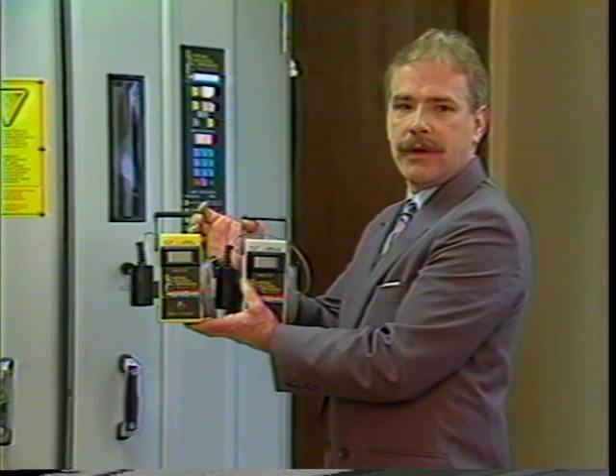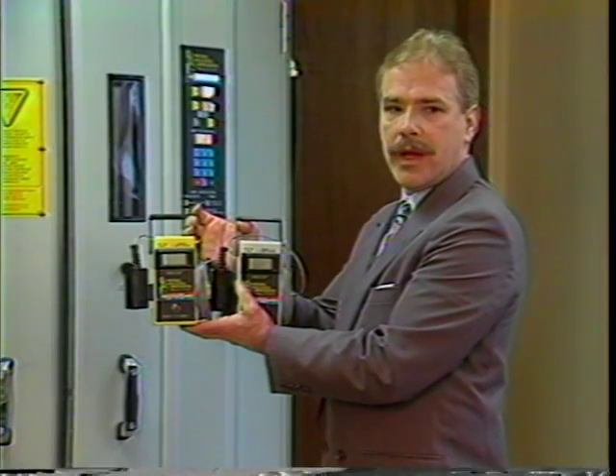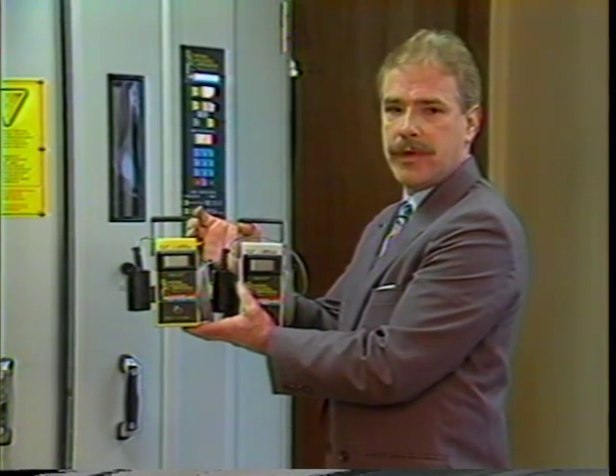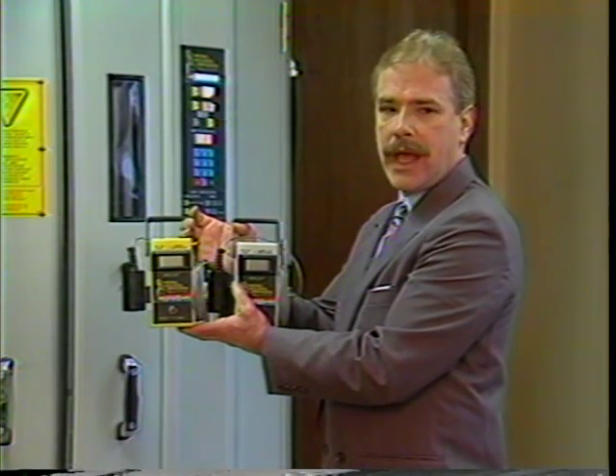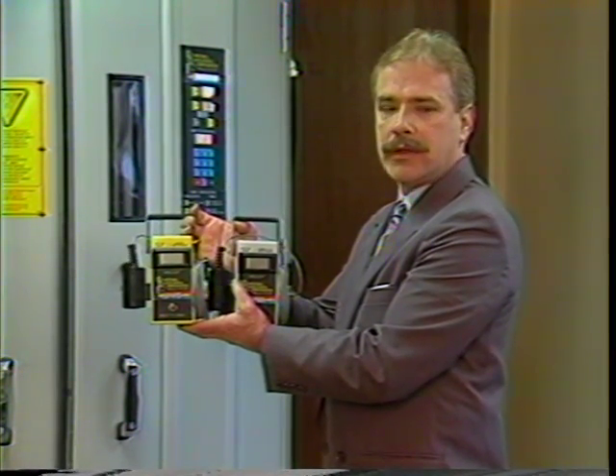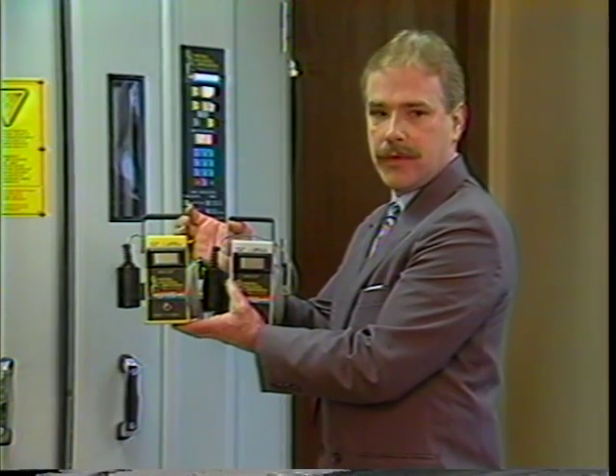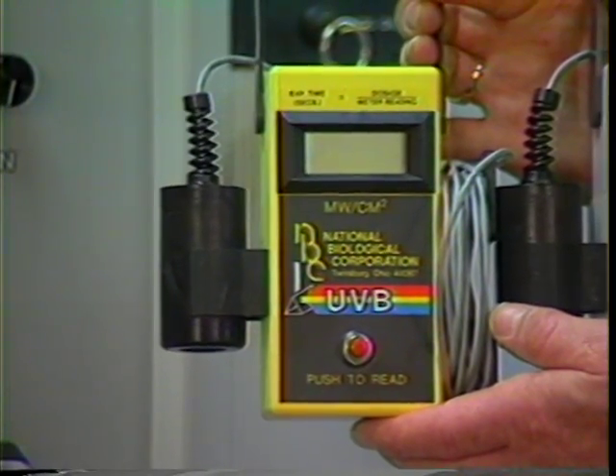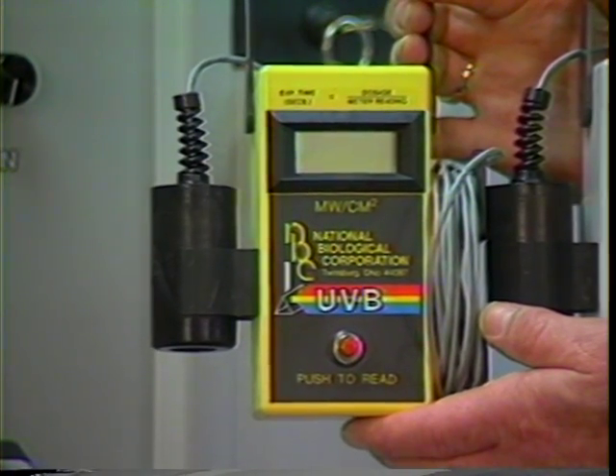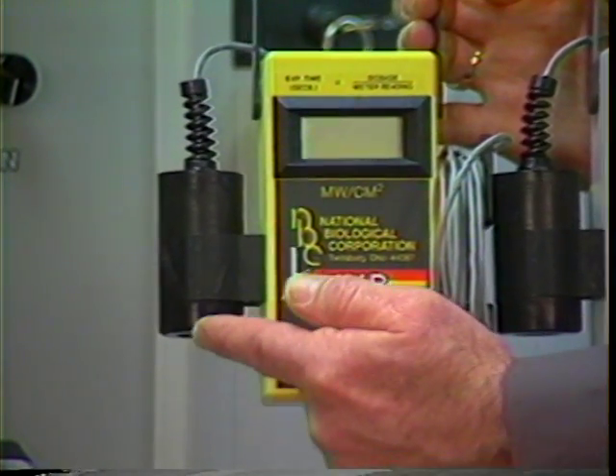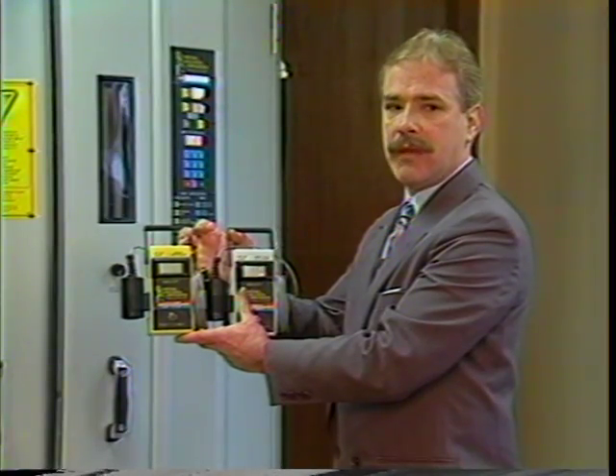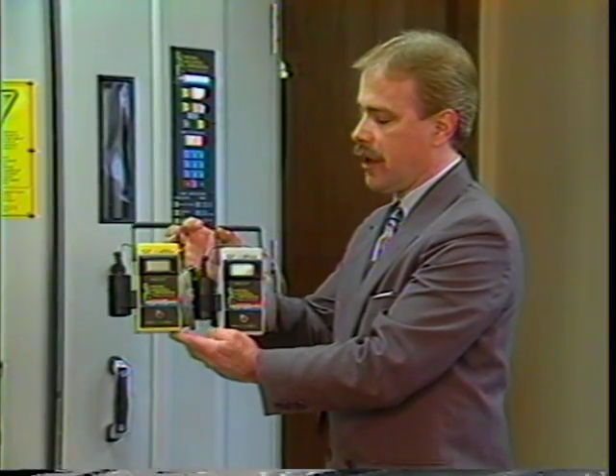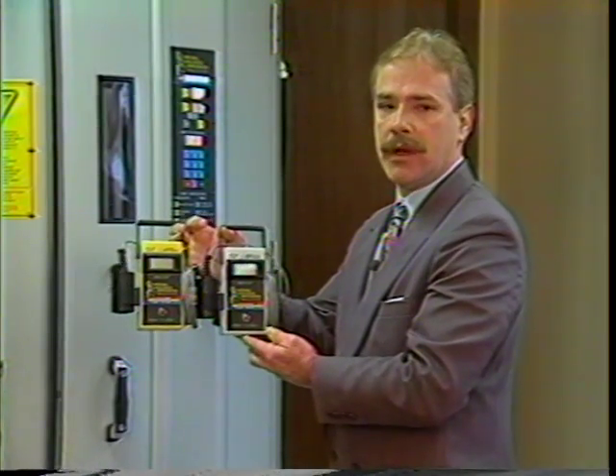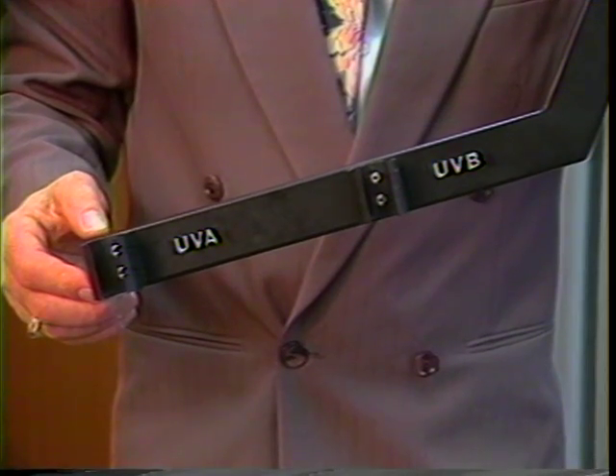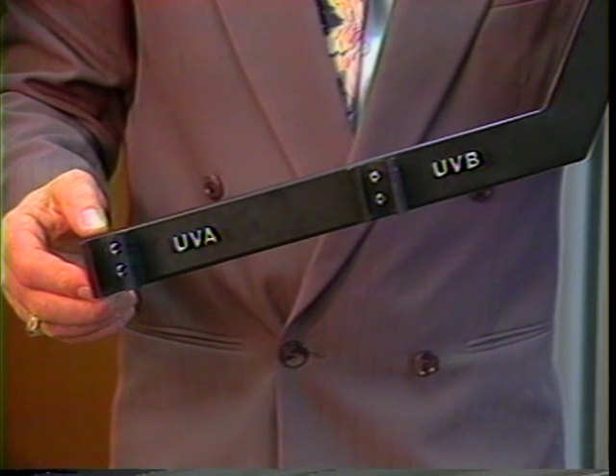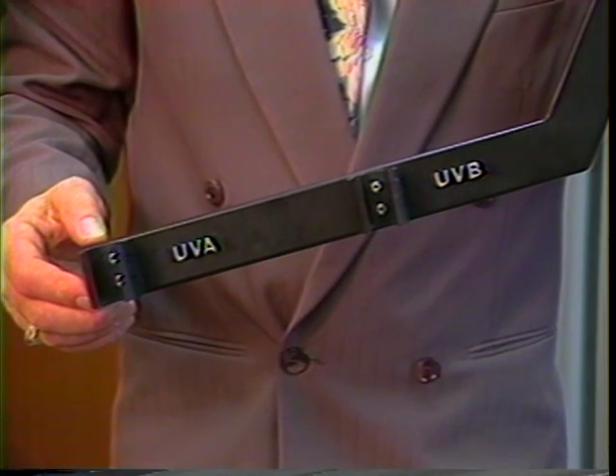Precise meter readings of ultraviolet A and ultraviolet B radiation are necessary to determine accurate treatment procedures. The handheld UVA and UVB metering devices are included with every HOUVA II combination unit. They contain a probe which houses sensors which read the energy emitted by the lamps in the unit. For purposes of identification, the UVB meter is housed in a yellow case and the UVA meter is housed in a gray case. A metering bar is used to properly position the meter's probes inside the unit.